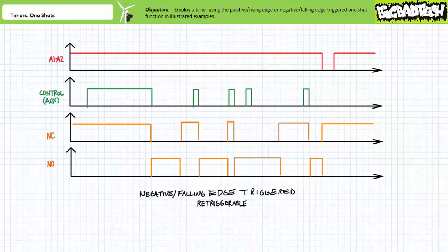Finally, in the interest of completeness, here's yet another timing diagram, only this time for an externally powered, retriggerable, negative edge triggered one-shot set for 5 seconds without a reset. Again, this is an externally powered, retriggerable, negative edge triggered one-shot without a reset. As previously, the only real difference is when this retriggerable one-shot experiences a triggering event followed by another triggering event during an ongoing one-shot. The retriggerable one-shot, instead of ignoring the additional input, basically extends the one-shot as we'd expect.